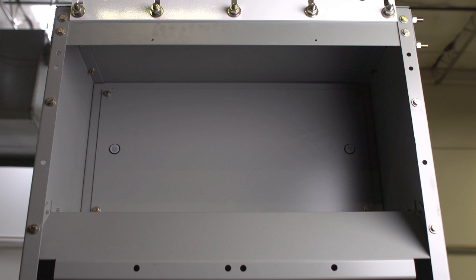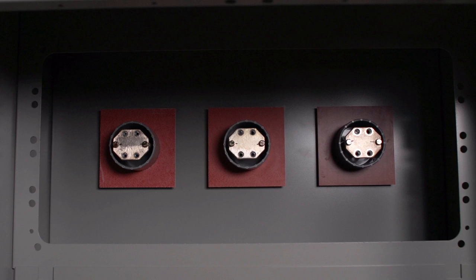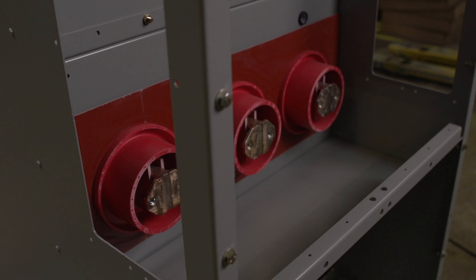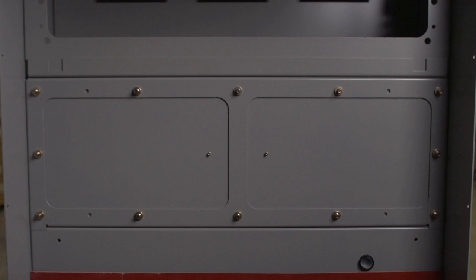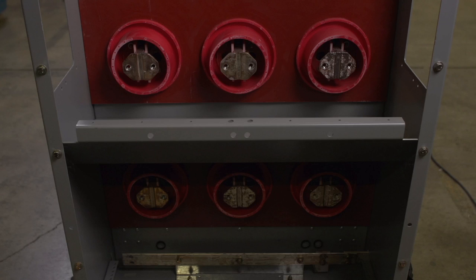Moving down to the D compartment, here are the bushings that provide a connection point to the primary bus bars. This big open rectangular space on the side of the skeleton is where the horizontal bus bars would be to connect one section to another. This is the low voltage compartment, so this is left empty. These upper circuit breaker bushings connect to vertical bus that then connects to the main horizontal bus. And, all the way at the bottom, we have the runback connections for the circuit breaker.